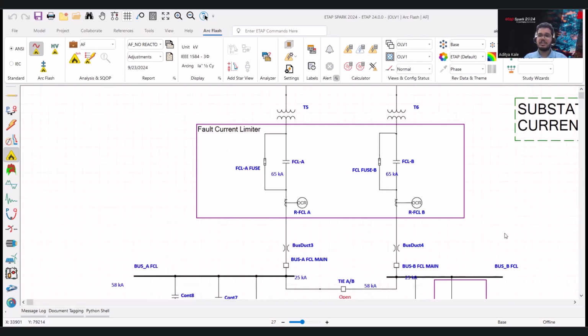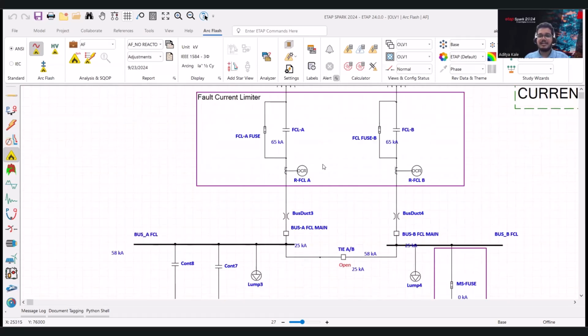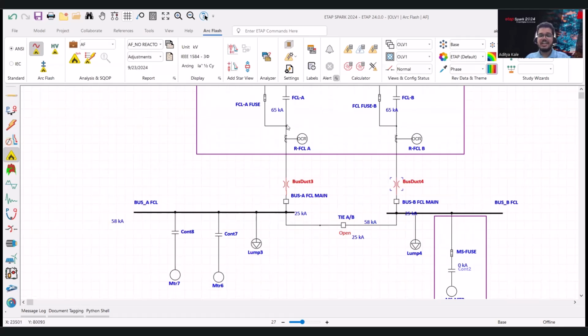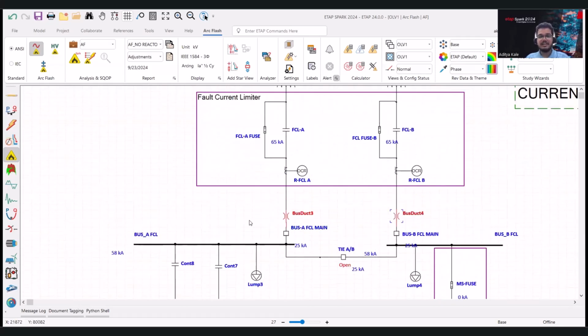Another thing to note here is the placement of these fault current limiters. Because these are placed on the secondary of the transformers, we get something that is desired by many arc flash mitigation techniques, which is low incident energy on the line side of the main breakers. So right now, the whole substation, including the line side of the main breakers, has low incident energy thanks to the fault current limiter.